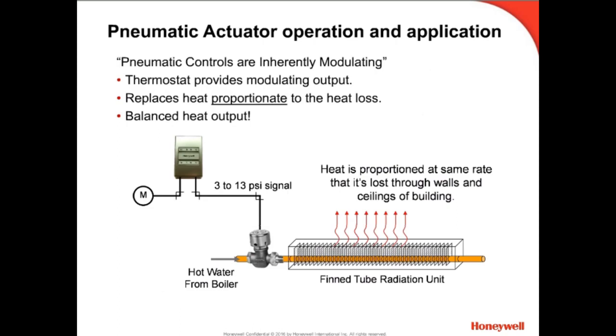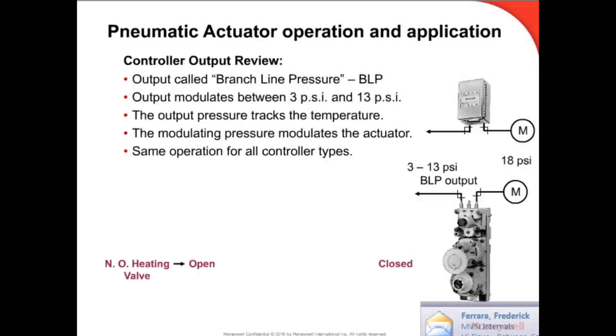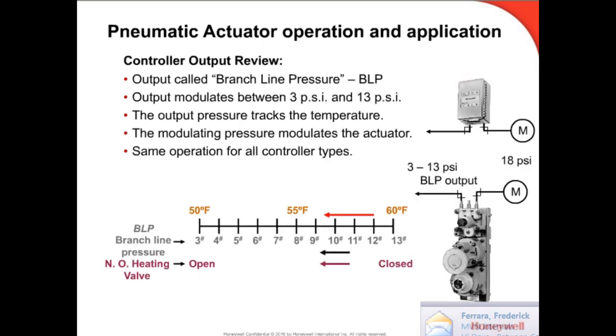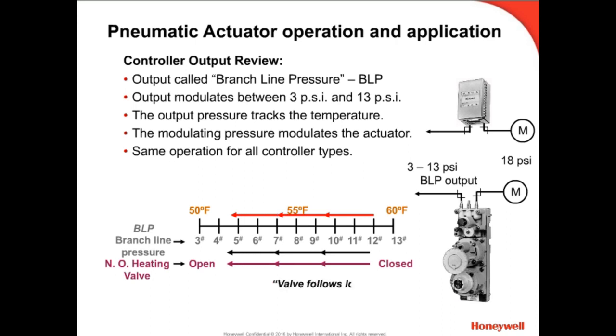In our last video, we discussed how a pneumatic controller modulates its output to proportion the right amount of heating or cooling. This whole concept is dependent upon the actuator's ability to smoothly apply this modulating signal to the damper or valve. The pneumatic system usually operates at 20 psi, and the pneumatic controller controls the outlet pressure, called branch line pressure, or BLP. It's this modulating branch line that then modulates an actuator to complete its task of positioning valves or dampers proportionally.